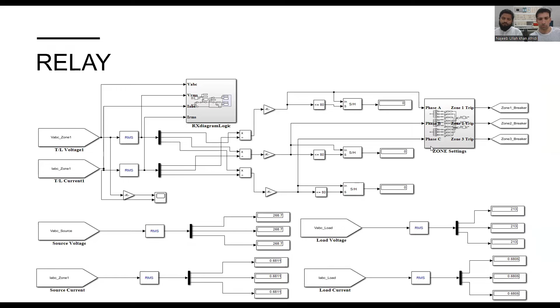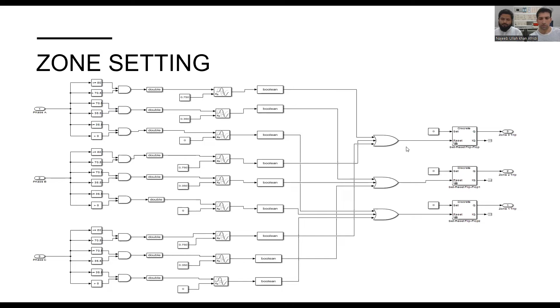This is the distance relay logic. In the distance relay logic, we take current and voltages during fault conditions, then extract impedance, and we convert that impedance to distance, and then we compare if the distance lies in a tripping zone. So the relay generates a trip signal according to the zone selection. In this we did a zone selection so that if the fault lies in the third zone, it will take a delay of 750 millisecond. If the fault lies in the second zone, it will take 350 millisecond. If the fault lies in the first zone, it will trip instantaneously and generate a trip signal for the breaker.